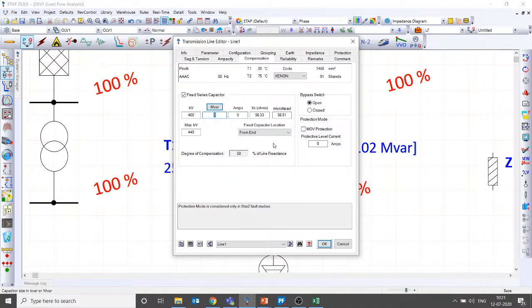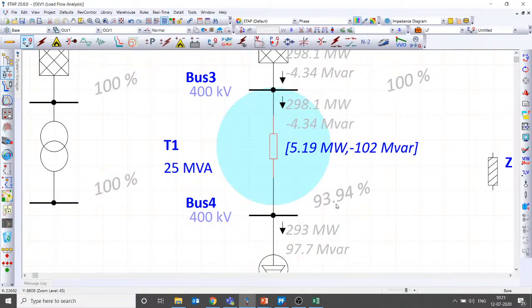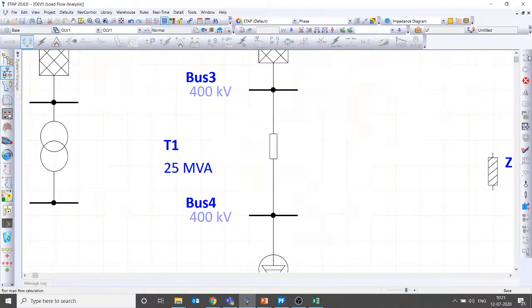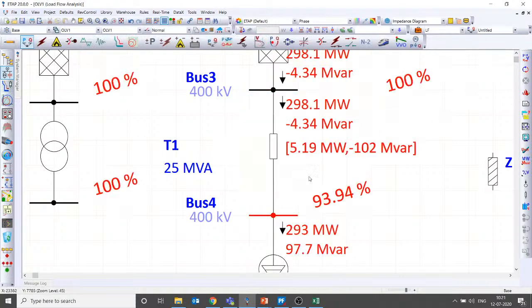MVR, probably you can find out the current and you can enter the MVR. Say assume that current carrying capacity of that 400 kV line is 1000. Yep. It can have 168 MVR. This is a fixed series compensation. Bypass switch is open, so it should impact positively, but unfortunately it is not doing.